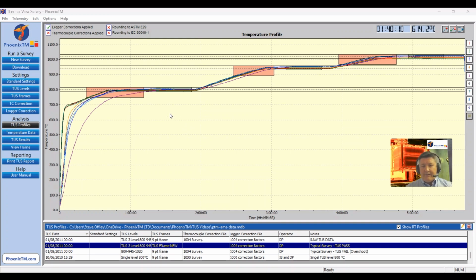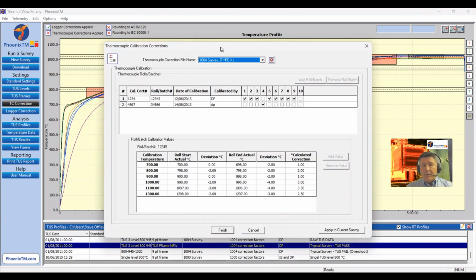To apply a correction factor file, I simply go to the TC connection correction button, and I'm going to call up from the list the appropriate thermocouple calibration correction factor file for the run I've just performed, and it's in fact this case here with file 1004. So if I click on that, I can see now the data that has historically been put in for the correction factor file. So for the run, which is a 9-point TUS, thermocouples 1, 2, 3, 4 through to 9 are all from one batch of cable, calibration certificate 1, 2, 3, 4, and one thermocouple, number 4, was from a second batch of cable, which was calibration certificate 4, 5, 6, 7.